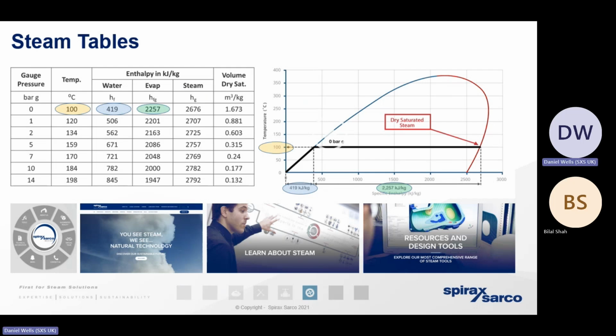In reality, our client's generating steam under pressure. So at 10 bar gauge, because of that pressure, the boiling point is higher. Therefore, the temperature of the steam is higher. Because of the pressure, the water's got to contain more energy before it boils. We don't need to add as much energy to that boiling water to make it evaporate, but the steam has still got a higher total energy content. And of course, because of the pressure, we've really compressed the volume of the steam. So it's now really cost effective for us to distribute it a long distance in a small pipe diameter with a lot of motive energy to it.